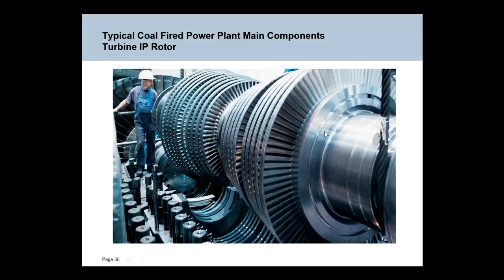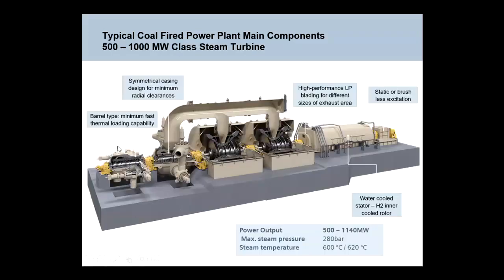This is a picture of an IP, intermediate pressure rotor, that's being lowered into the casing. You can see a man here to give you a feel for the scale. So the complete machine train, if I go back, this complete machine train of HP rotor, IP rotor, two LPs and generator rotor will weigh several hundred tons. It rotates at 3,000 RPM in a 50 Hertz system and is fitted inside the casing with 0.2 of a millimetre clearances. So this is some pretty special mechanical engineering to make this thing work.